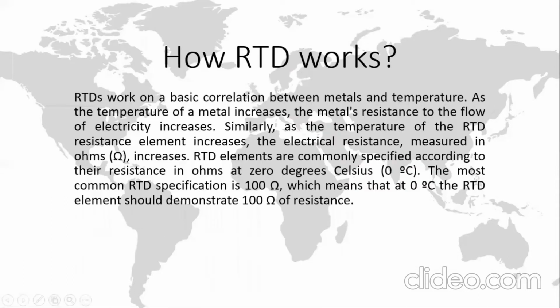So how does an RTD work? RTD works on the basic correlation between metals and temperature. As the temperature of a metal increases, the metal's resistance to the flow of electricity increases. Similarly, as the temperature of the RTD resistance element increases, the electrical resistance measured in ohms also increases.